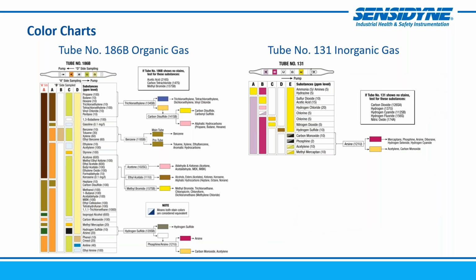So here you can see those 2 tubes on that color chart. It's tube number 186B. This really determines your organic gases that could be present. And then the tube 131 is really used for determining inorganic gases. And you can see that there's 5 different sections within that tube, that each one of those sections, depending on the color stain change for that section, will indicate a different inorganic gas group. And then similarly on the 186B for the organic gases, depending on the color change within that section, you would be able to determine what organic gases are present in that unknown gas stream.